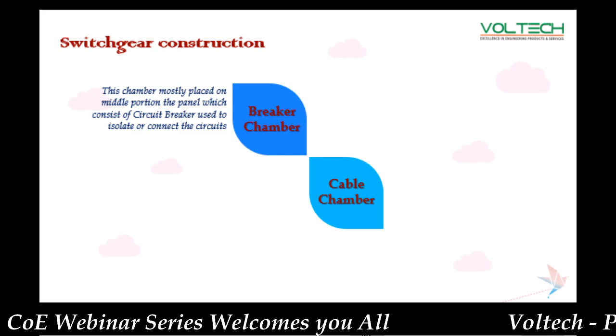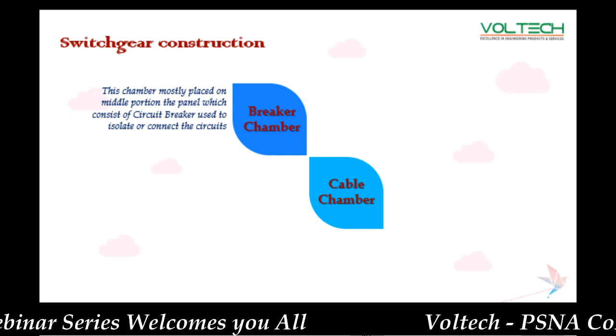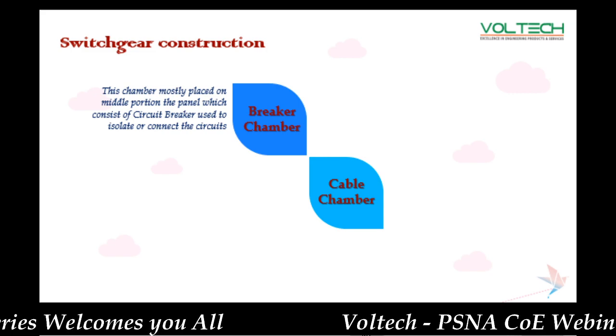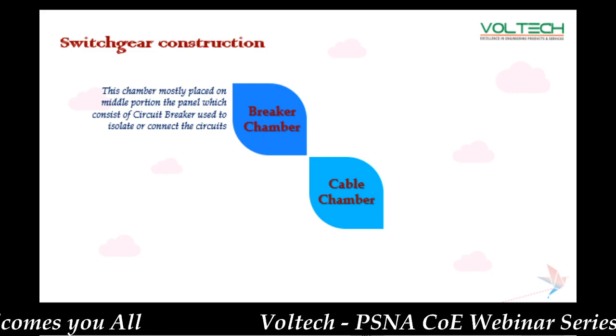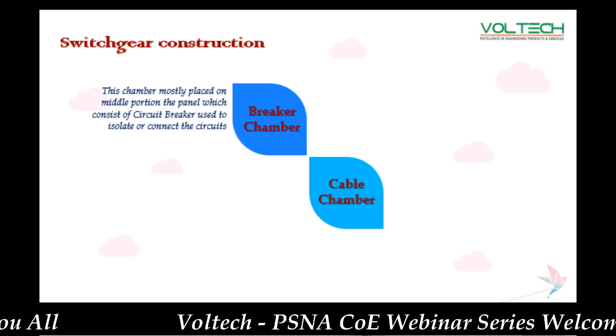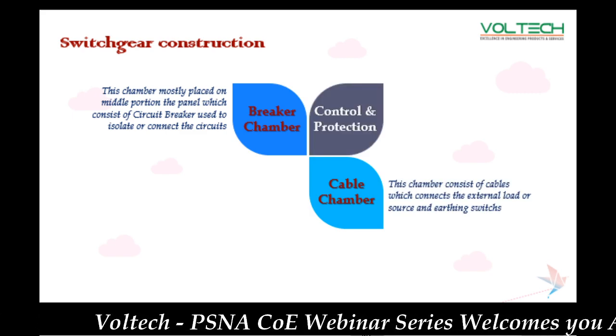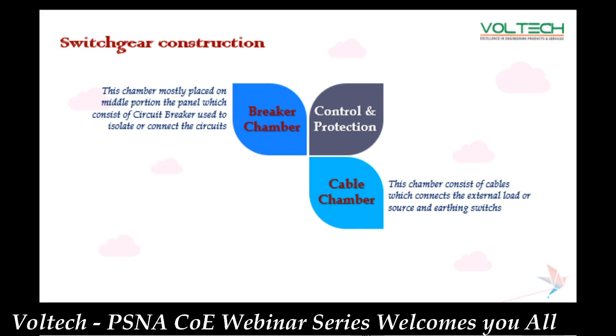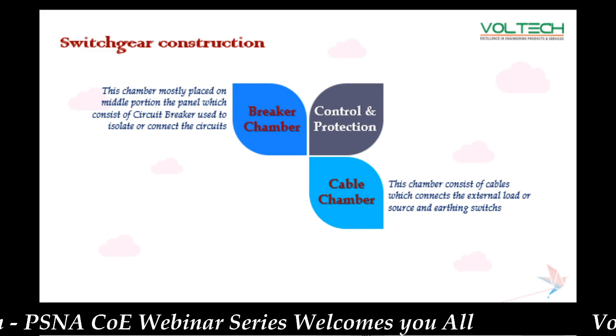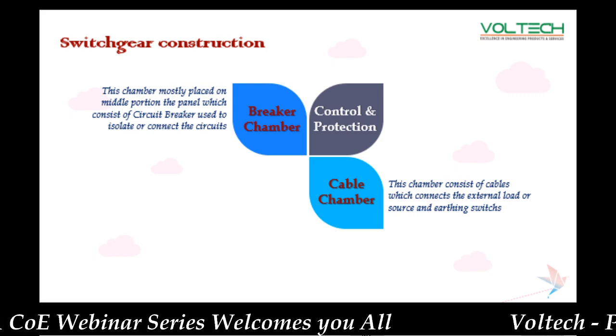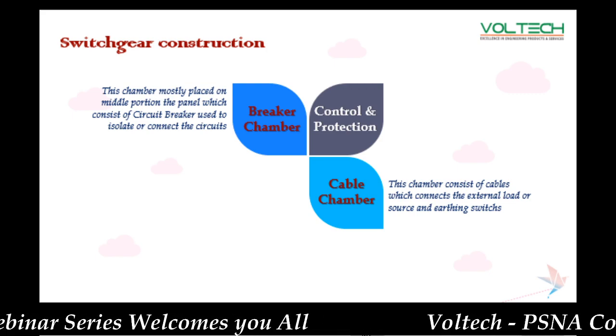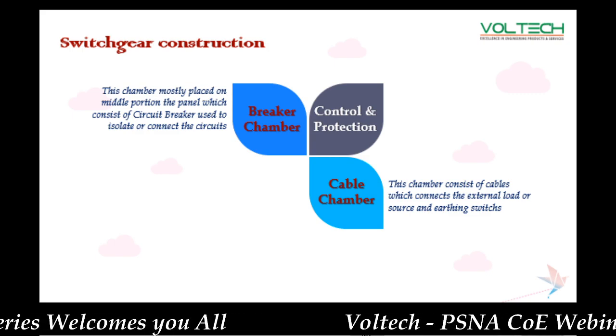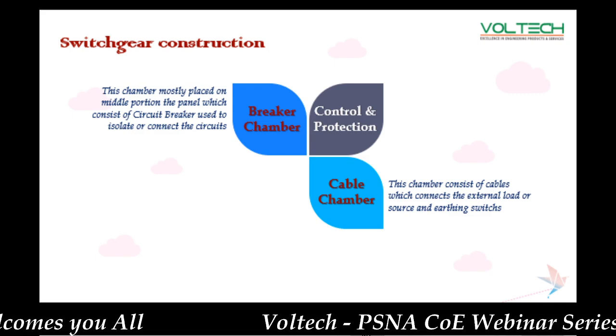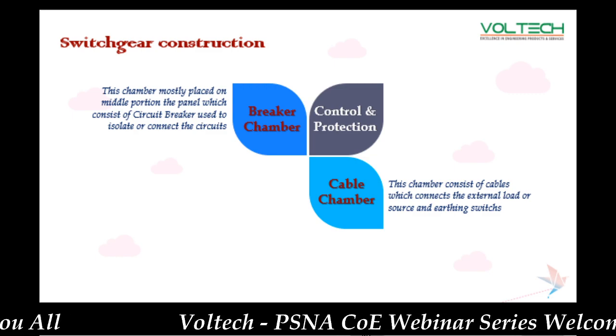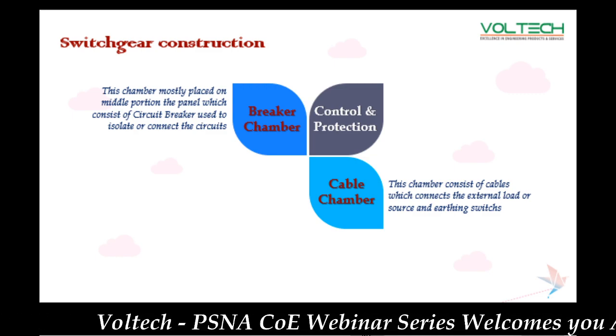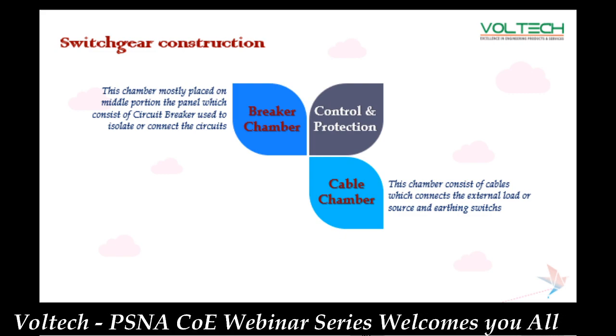Next is the cable chamber, which is the exit or entry point of the switchgear, used to evacuate power through cables or take input through cables. Next is control and protection - meaning we have to operate and isolate the circuit breakers during a fault. So we place control relays or protection relays on the panel, used for fault detection, isolation, and manual operation.